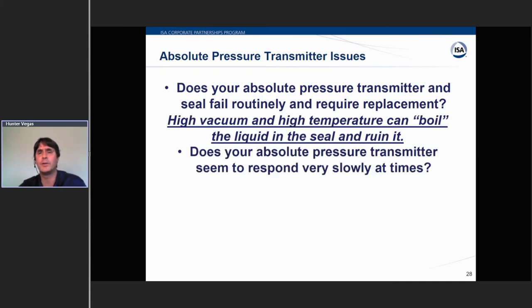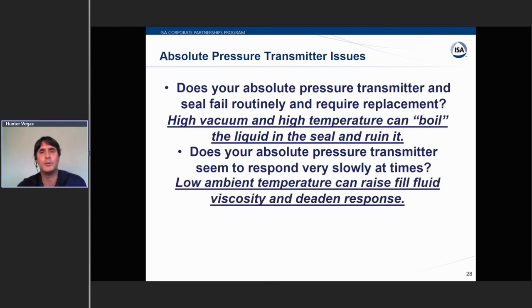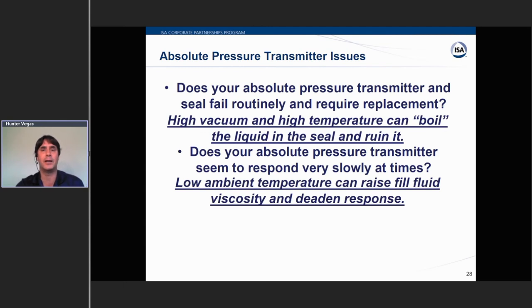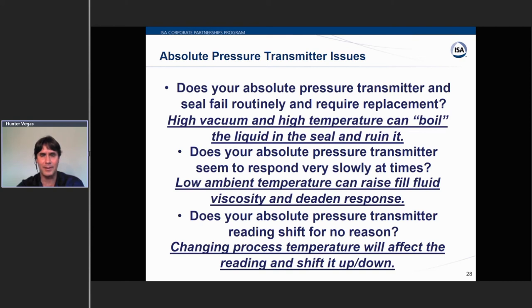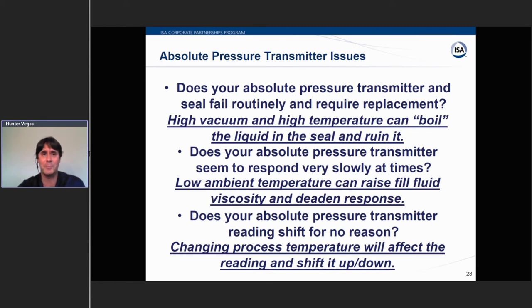If your absolute pressure transmitter responds very slowly, that's often low ambient temperature raising the fill fluid viscosity and deadening the response. If the reading shifts around for no reason, changing process temperature heats up the fill fluid, it expands, and the transmitter sees that as pressure — so the reading will move with process temperature. All of these will make your calibration seem wrong, but it isn't your calibration. There are ways to fix these issues, but you won't calibrate your way out of them.